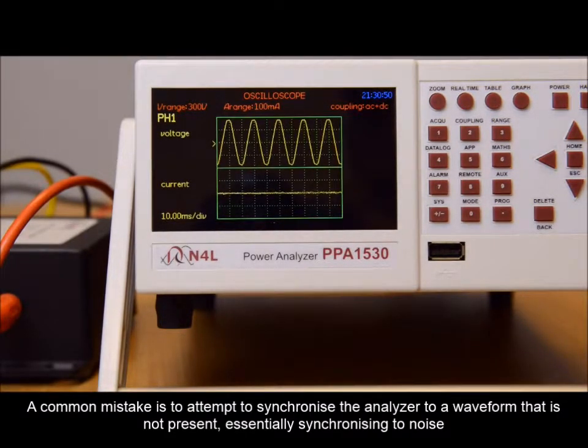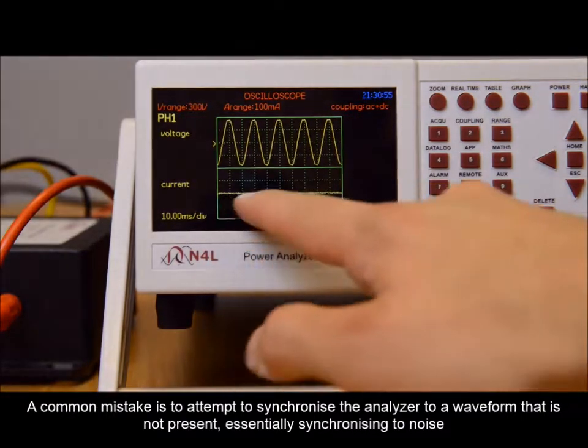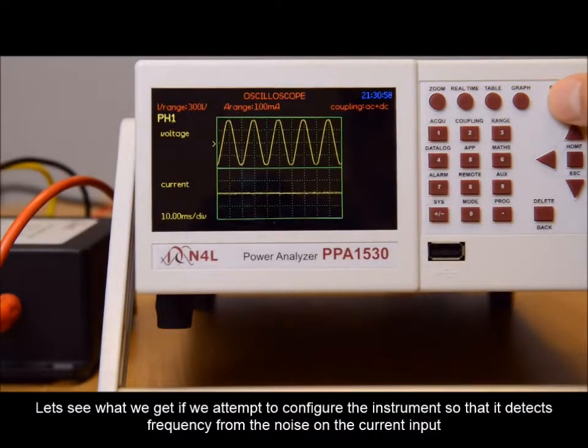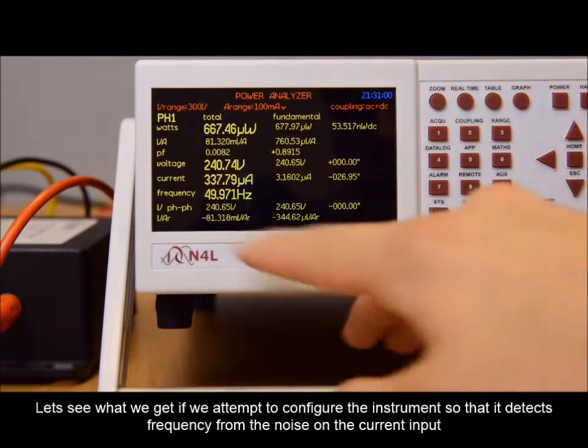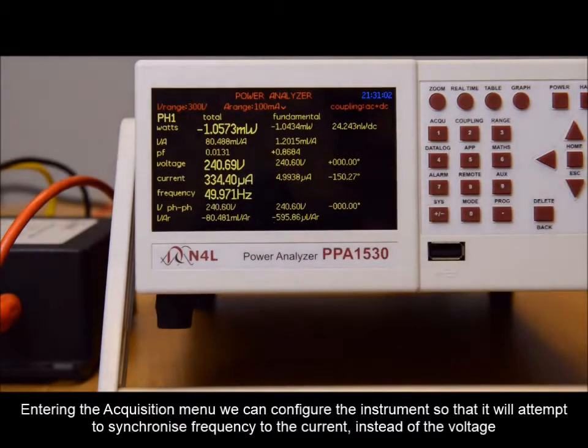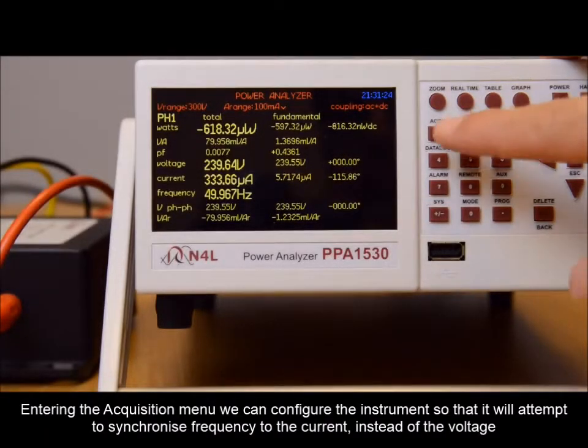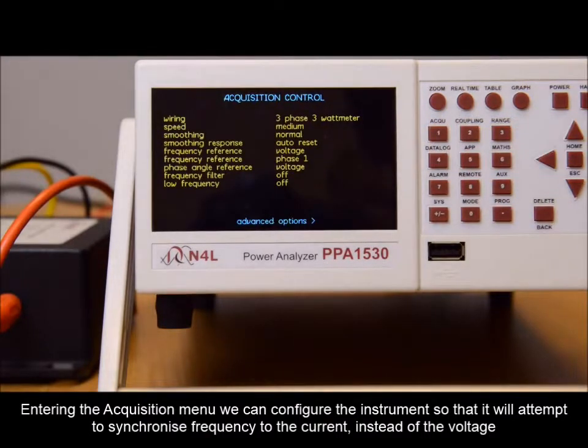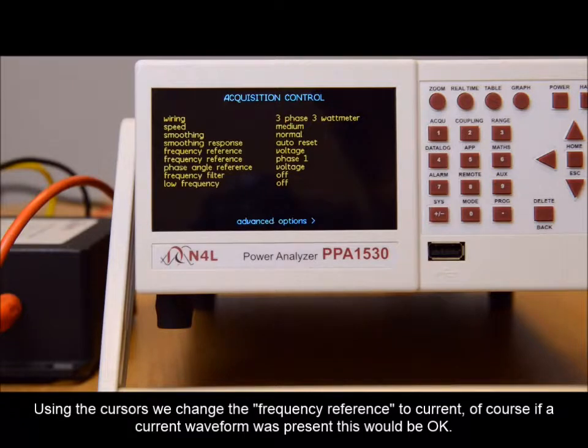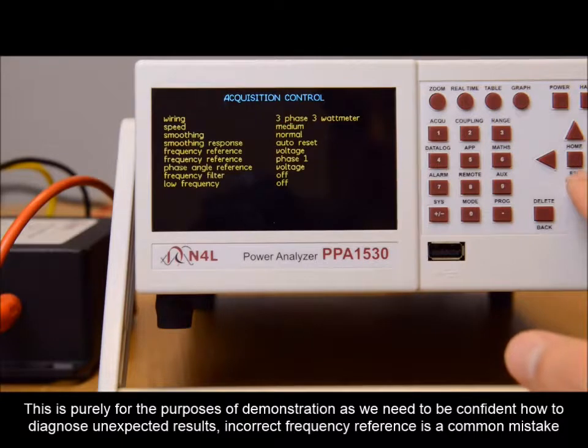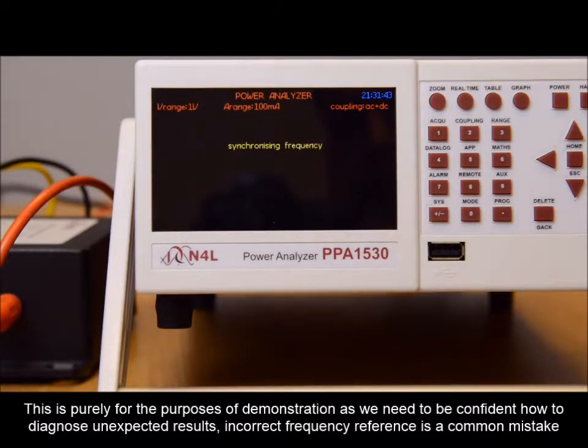A common mistake is to attempt to synchronize the analyzer to a waveform that is not present, essentially synchronizing to noise. Let's see what we get if we attempt to configure the instrument so that it detects a frequency from the noise on the current input. Entering the acquisition menu, we can configure the instrument so that it will attempt to synchronize frequency to the current instead of the voltage. Using the cursors, we change the frequency reference to current. Of course, if a current waveform were present, this would be okay. This is purely for the purposes of demonstration, as we need to be confident how to diagnose unexpected results. Incorrect frequency reference is a common mistake.